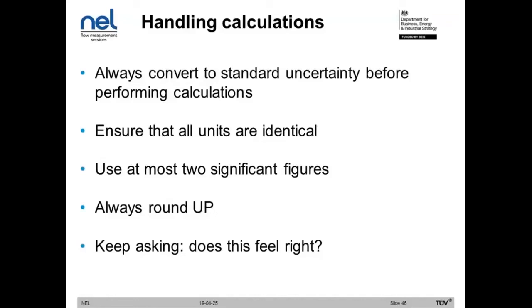And the whole way through the process, you have to think, does this seem correct? Generally, when you do the first pass of the uncertainty budget, you'll probably find that your values are much too optimistic, and your overall uncertainty isn't achievable based on worked experience and what you know about the system. The reason for this is that you haven't considered enough uncertainty sources, or you haven't applied the correct value to each of them. But generally speaking, after further revisions, the uncertainties tend to increase rather than decrease. If you do want to decrease the uncertainty of the system, you can improve the choice of measurement devices, or you can collect additional information that allows you to refine your estimates. But generally speaking, it's a pessimistic and conservative process.